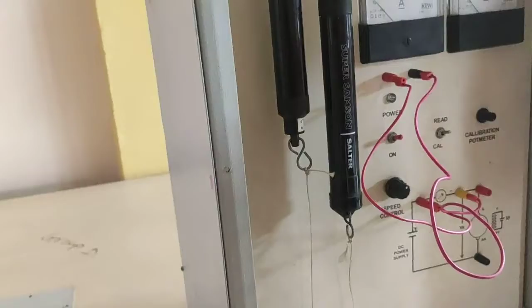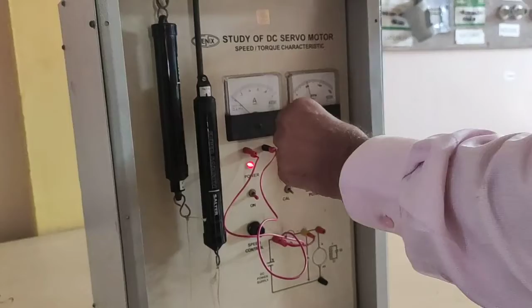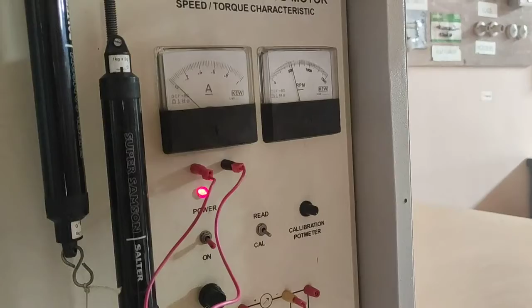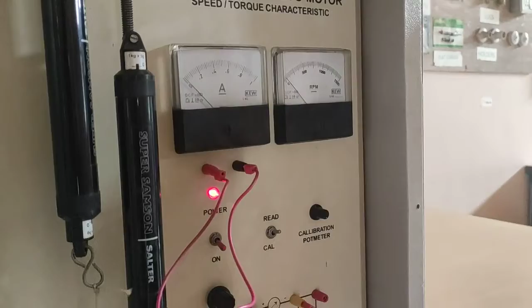We have made the power on. Put the read/cal switch to the calibration position and adjust the calibration pot to get 500 rpm. We have adjusted it to 500 rpm, and once calibrated, throw the switch back to the read position.